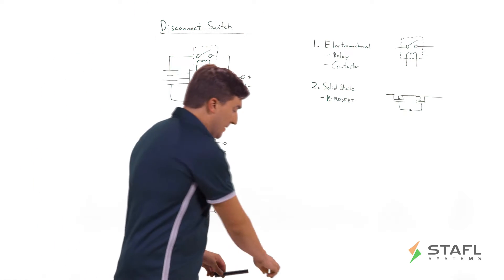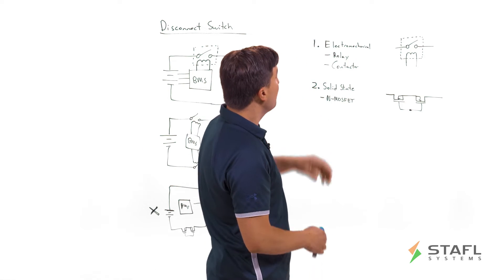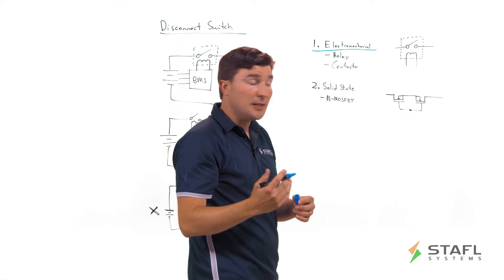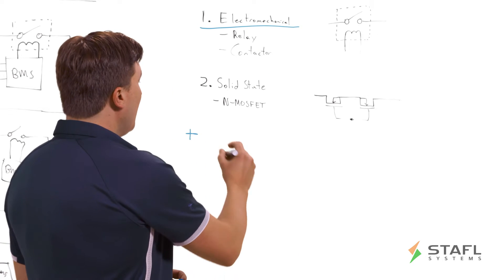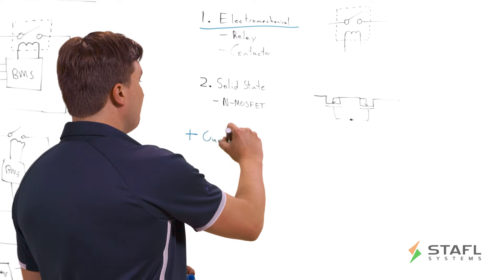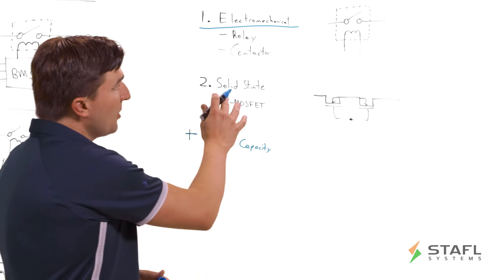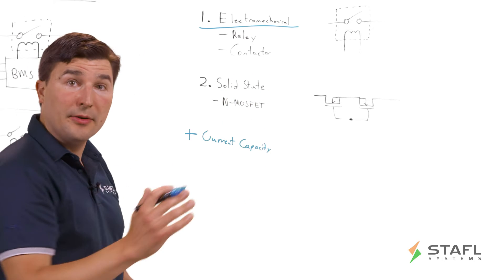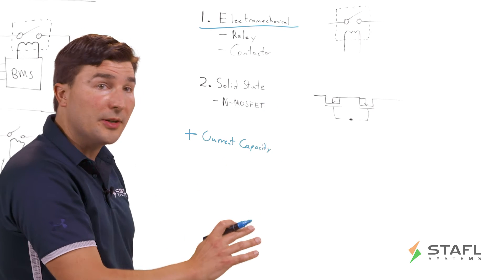Let's discuss some of the benefits and the pros and cons of each of these approaches. Starting with electromechanical, what are some of the characteristics that are beneficial? One is that you have very high current carrying capacity. For example, you could easily have a contactor that can handle 500 amps, 600 amps, even 1000 amps, whereas doing that in solid state would be very challenging.